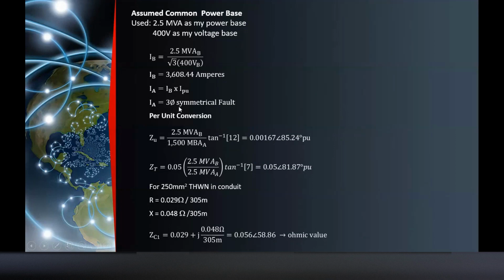Okay? So after you establish your base values, you have to convert all the equipment to per unit values. For the impedance of the utility, we have the formula MVA base divided by MVA actual. So you put 2.5 MVA as the base, divided by 1,500 MVA as the actual, and take the inverse tangent of the X over R to get the angle. So I will get 0.00167 angle 85.24 degrees per unit. Okay, so you have converted that to per unit.